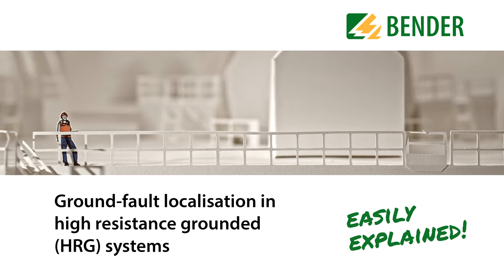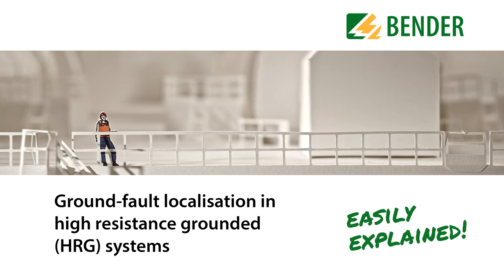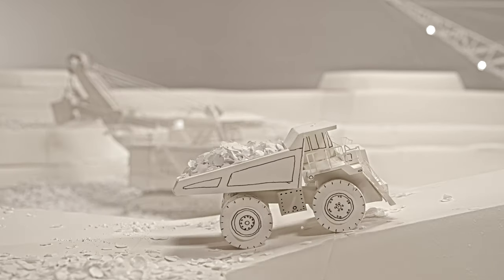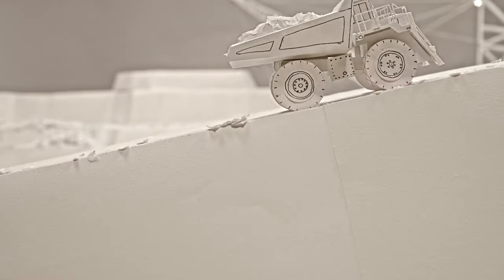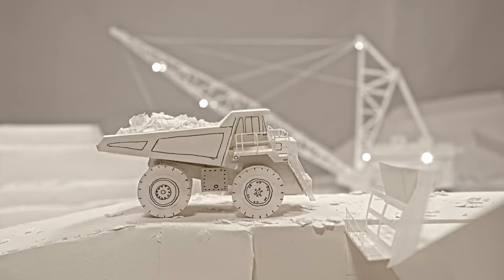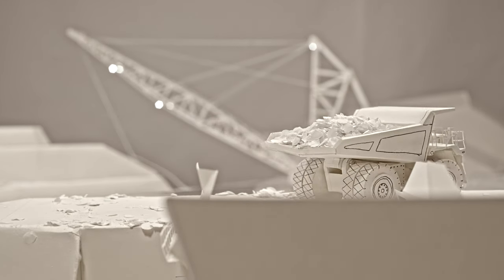Ground fault localization in high resistance grounded systems. Of course, the HRG system is also used in plant environments. Here the substations are not only feeding movable equipment but also often continuous processes.